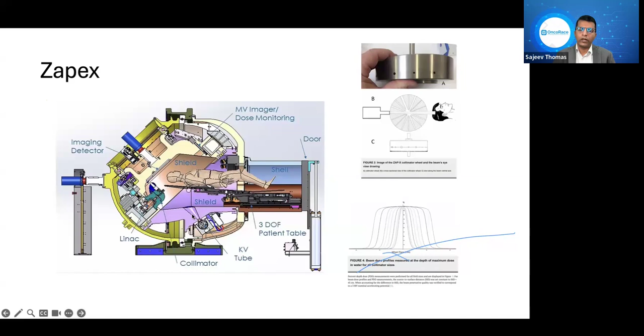It has an S-band LINAC with a 3 MV linear accelerator, which is optimized for radiosurgery and can deliver high dose per fraction, and a robotic patient positioning system with a 6 degrees of freedom couch and submillimetric accuracy for corrections, and a real-time imaging platform. It has an MV and kV platform and an integrated infrared and surface-guided tracking system. The treatment planning system has an inverse planning algorithm, known as Axon, and it is compatible with most imaging modalities. It also has many safety interlocks and integrated QA workflows, as we see with other systems.